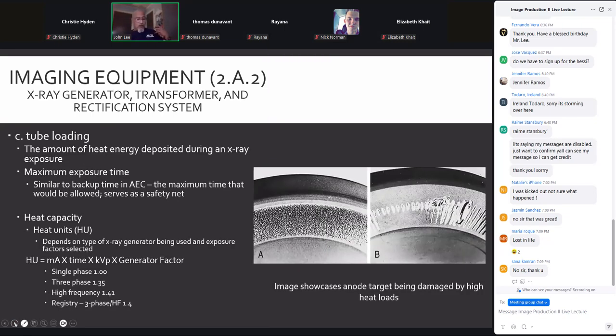Now, changing the voltage ripple, making it so that we have less, maintaining that kV as high as it could possibly be to peak, has its disadvantages. Its biggest disadvantage is the amount of heat that it loads onto the anode and the target. That's what tube loading is referring to. This is the amount of heat that's going to be deposited during the exposure into the anode.